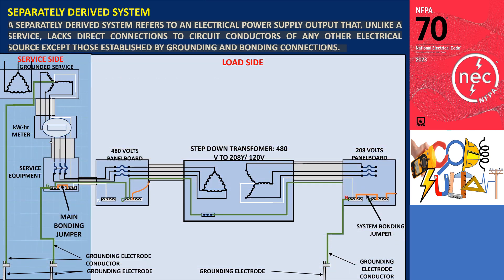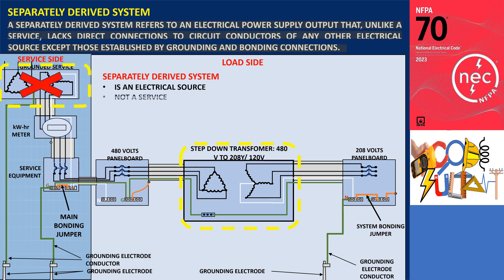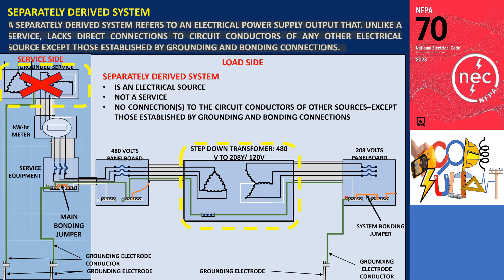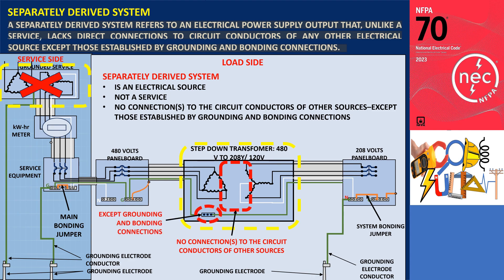The lack of direct connections applies except those established by grounding and bonding connections. Therefore, a separately derived system is an electrical source not provided by the utility or service — it has no direct electrical connection to the service-derived system, meaning no direct connection to circuit conductors of any other electrical source except those established by grounding and bonding connections.